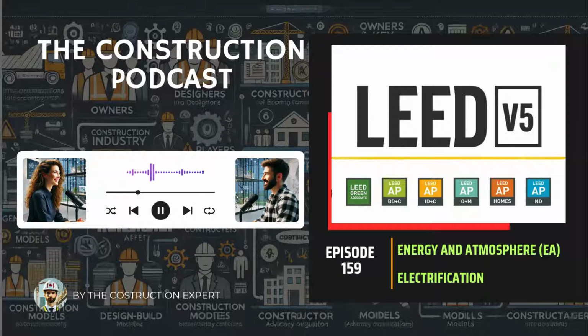Why is starting early so important? Because trying to retrofit later is almost always harder and way more expensive. Think about designing the electrical panel capacity, the ductwork pathways, the space for heat pump equipment. If you plan for it from day one, it's integrated smoothly. Right. And starting early means you can optimize the building itself first: super insulation, air tightness, high-performance windows. Reduce the heating and cooling load dramatically before you even size the electric systems. That means smaller, cheaper, more efficient heat pumps. It's about integrated design. Design the thermos before you choose the heater. Exactly. Get the architect, engineer, and builder talking about electrification from the initial concept sketches. Okay, start early. What's next?